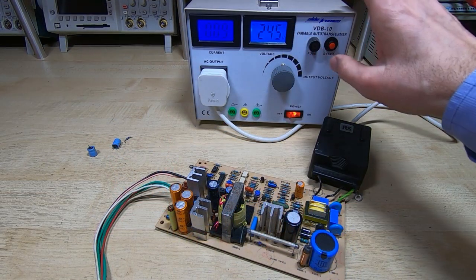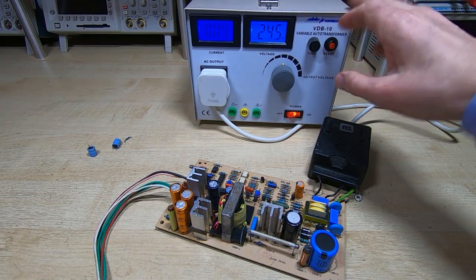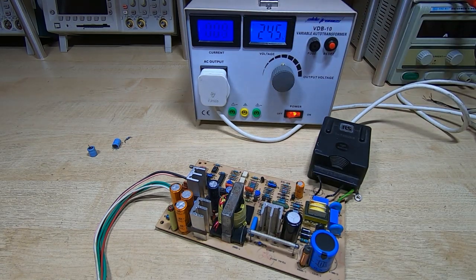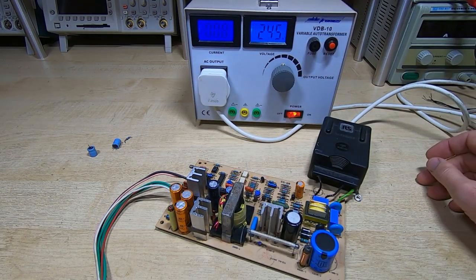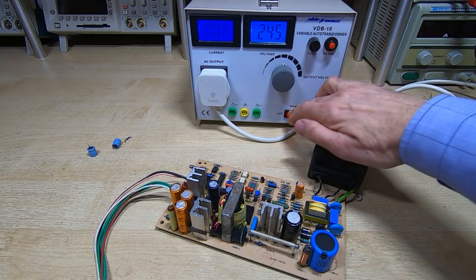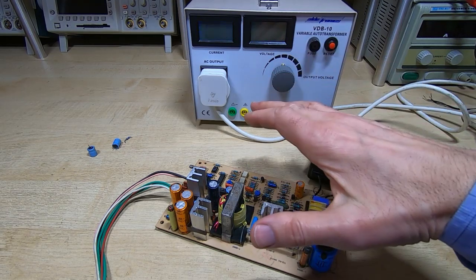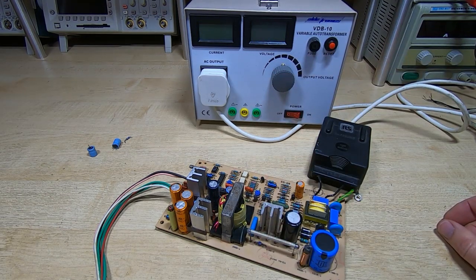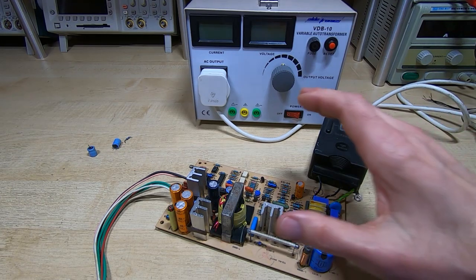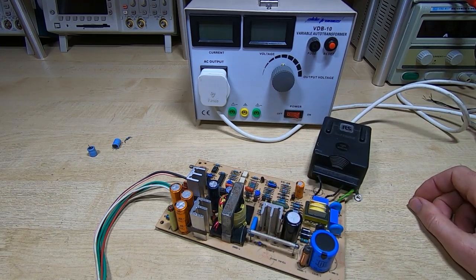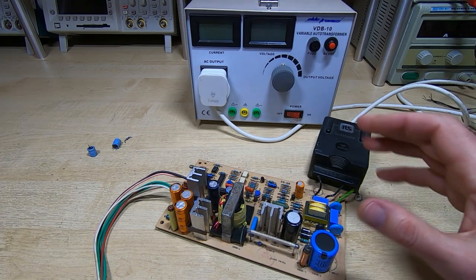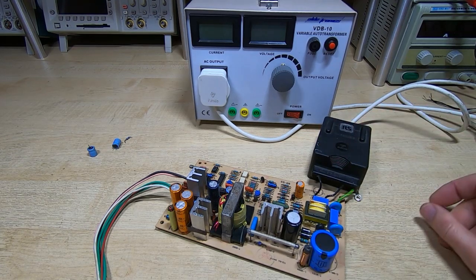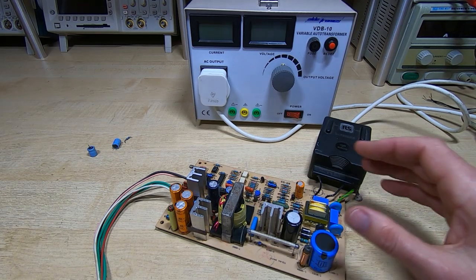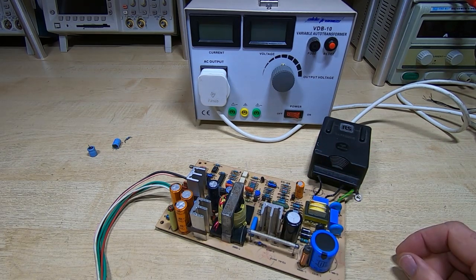I've got it running at 245 volts on the AC input. The current drawn is about 80-90 milliamps, which is correct, and the outputs are all correct. So what I'll do now is get this reassembled into the case. I won't show that, it's obviously fairly dull bolting these things back into metal boxes. Then I'll do a full power test before I send it back to its owner. If anything does crop up as a result of the testing, I'll put that on a video, but I'm fairly confident this is now resolved and sorted out.